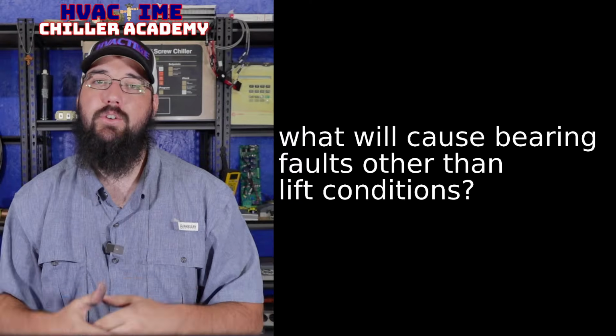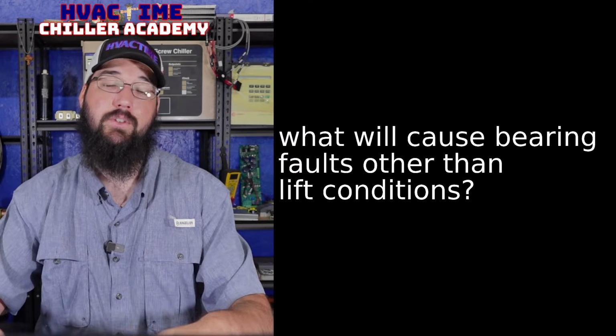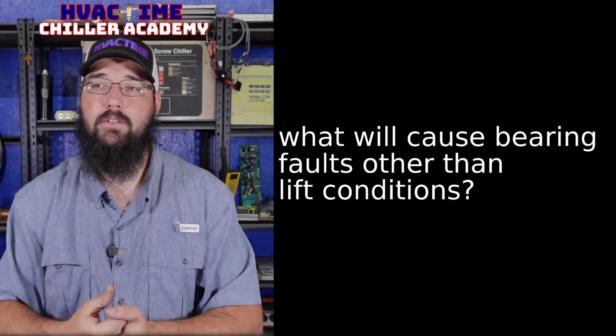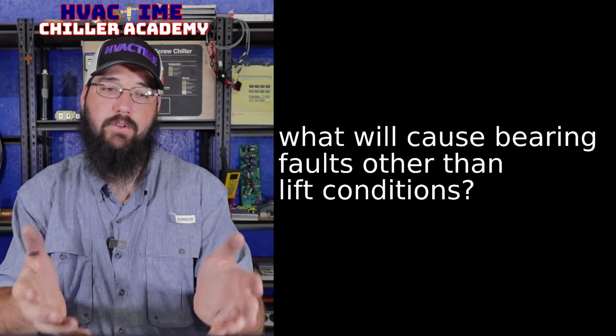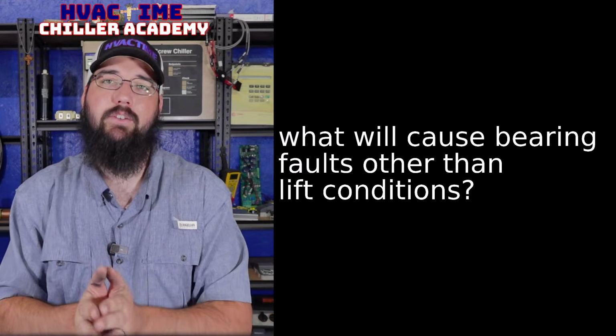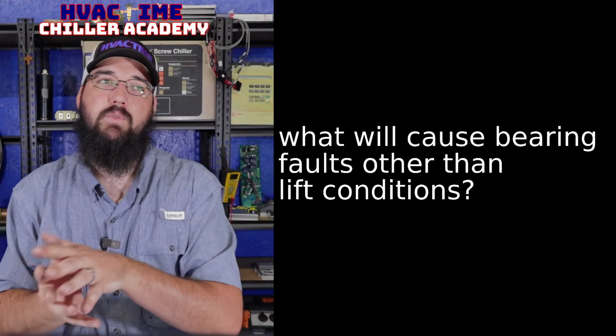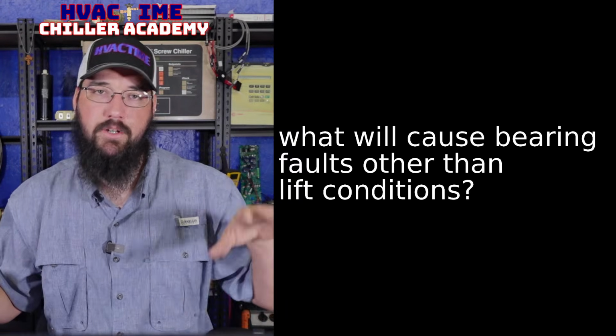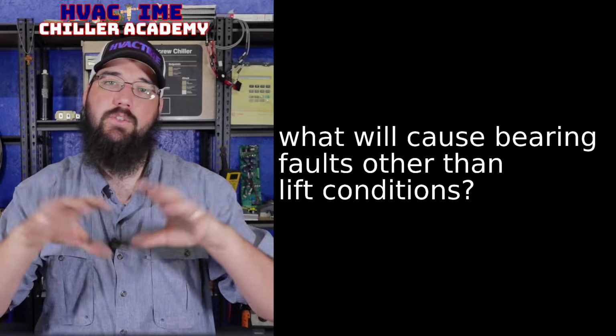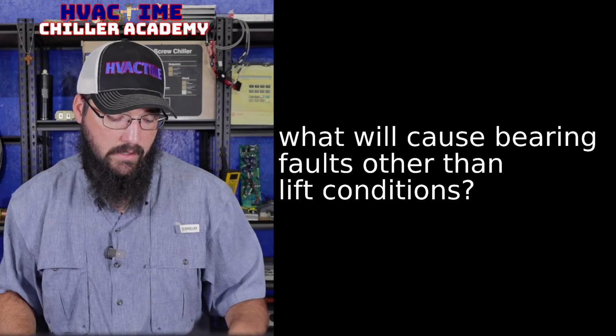Having stall and surge is external to the compressor. Fix those issues. Why are we stalling? Why are we surging? Okay, and we can address that. But in your case, you specified we're not having that issue. So then that leaves you with calibration or inverter, without just recommending the compressor as a whole.